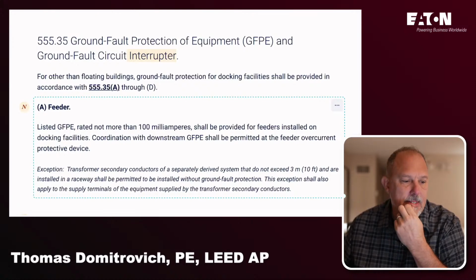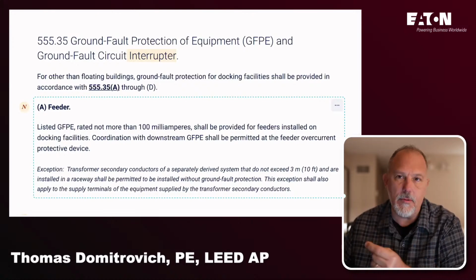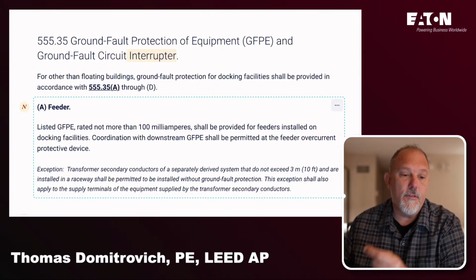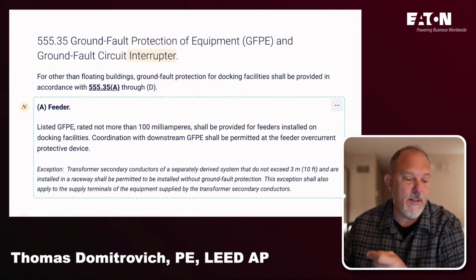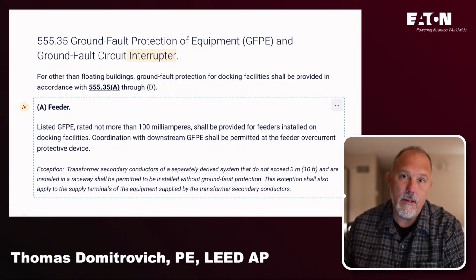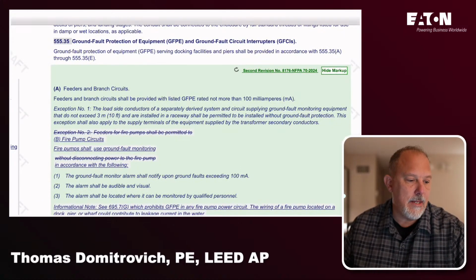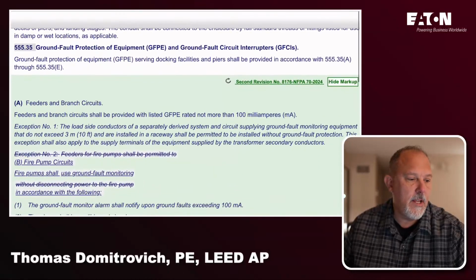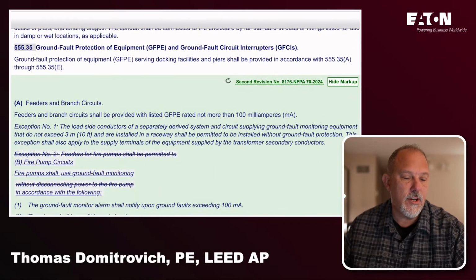No, it is right. Oh man, look at this. This is a great teaching moment. So look what this says. It says for other than floating buildings, ground fault protection for docking facilities shall be provided in accordance with 555.35A through D. So that is beautiful. But look what they did. They changed in the first draft, ground fault protection of equipment serving docking facilities and piers shall be provided in accordance with 555. So they changed it to a way that it just addresses GFPE.